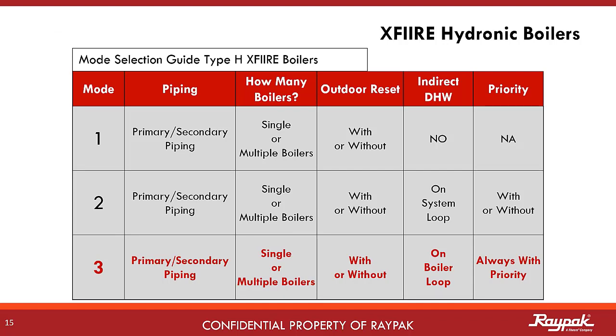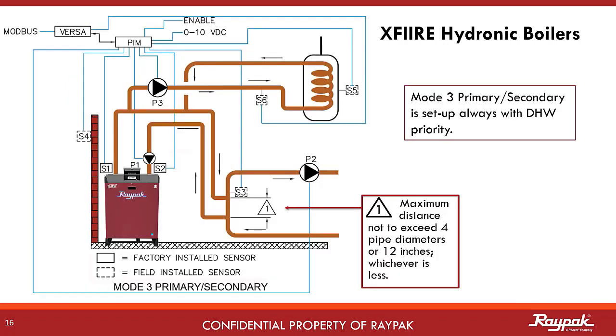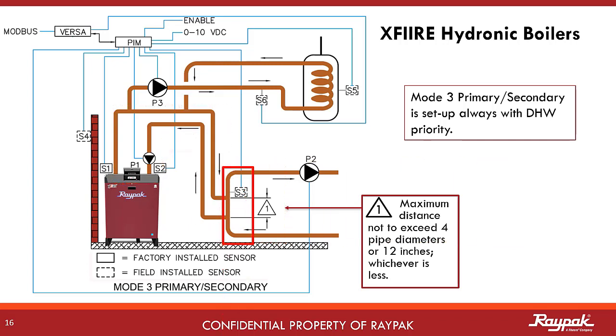Last for the hydronic modes, we have Mode 3 for primary-secondary systems. The key thing that makes this a Mode 3 is the indirect domestic hot water on the boiler loop. Mode 3 is always with priority. Here is a Mode 3 primary-secondary single boiler system. You have a boiler loop and a system loop. The decoupler is built in the same way to pressure-isolate the two loops, and the indirect domestic hot water heat exchanger is on the boiler loop in this case.